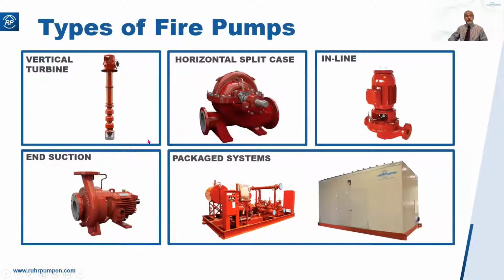These are the various pump types. The vast majority are horizontal split case. End suction and inline pumps are only for small flows, up to about 200 gallons a minute. Vertical turbine pumps are required whenever there would be a suction lift condition. You cannot use a horizontal split case pump on suction lift per NFPA-20. Package systems are particularly popular now for oil and gas installations in particular, and we will look at several such installations.